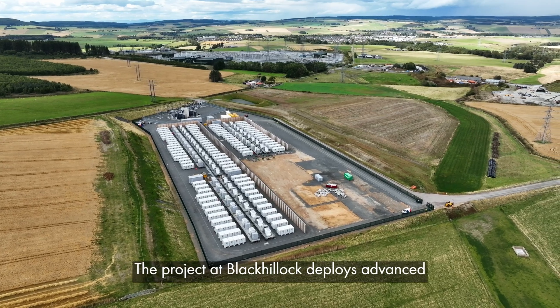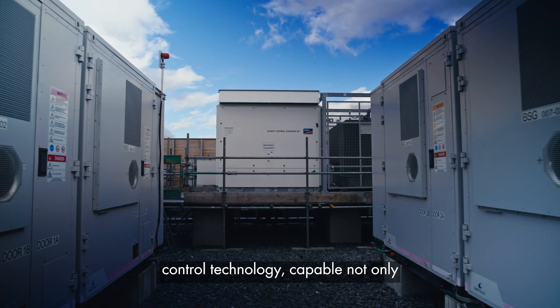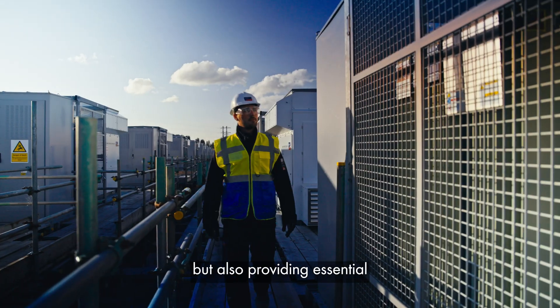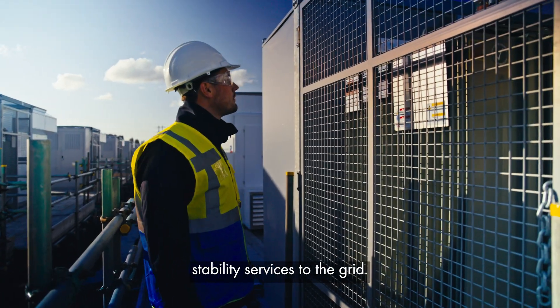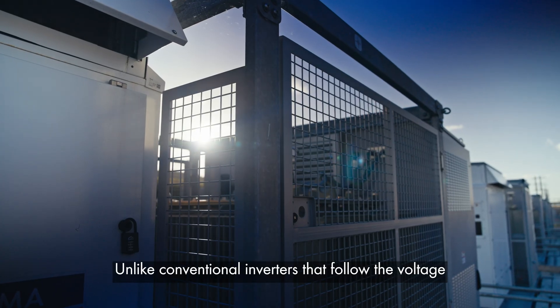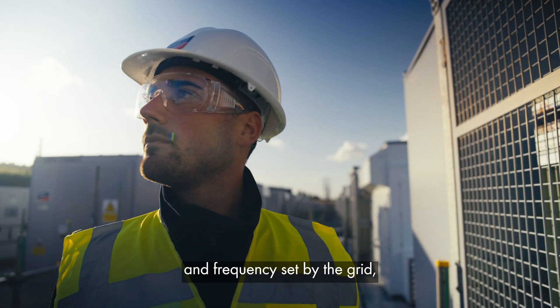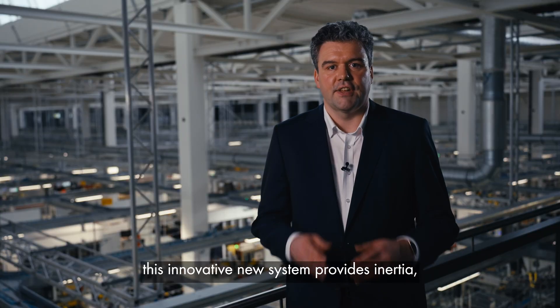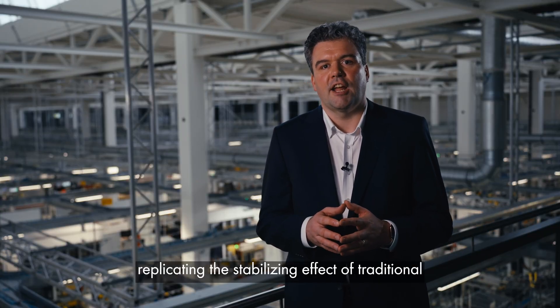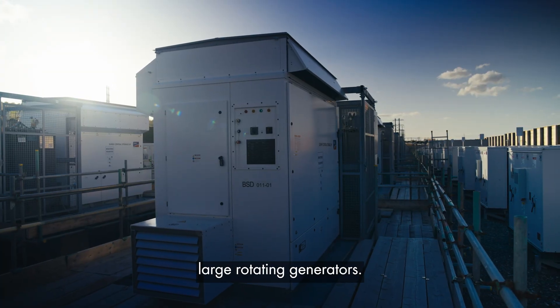The project at Blackhillock deploys advanced control technology capable not only of storing and releasing energy, but also providing essential stability services to the grid. Unlike conventional inverters that follow the voltage and frequency set by the grid, this innovative new system provides inertia, replicating the stabilizing effect of traditional large rotating generators.